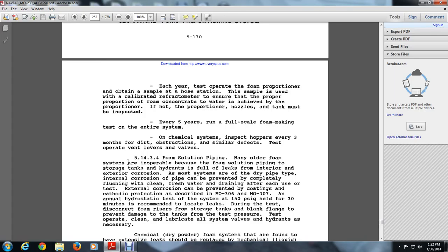5-1-4-3-4, foam solution piping. The main cause of the system being inoperable is the foam solution piping, the storage piping, and the hydrants: leaks, interior and exterior corrosion. Most systems are of the dry pipe type. Interior corrosion of the pipe is prevented by completely flushing it clean with fresh water and draining after use. For external corrosion, use preventing coatings and cathodic protection as described in MO 306 and MO 307.